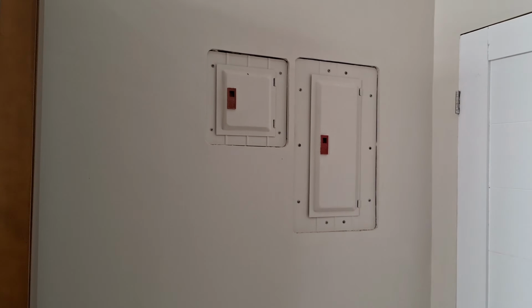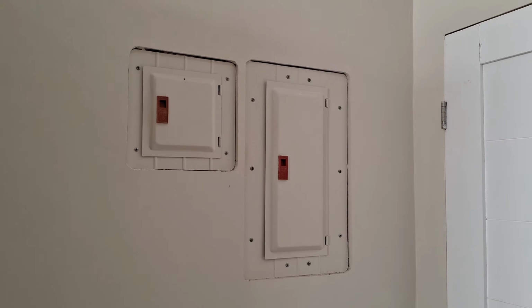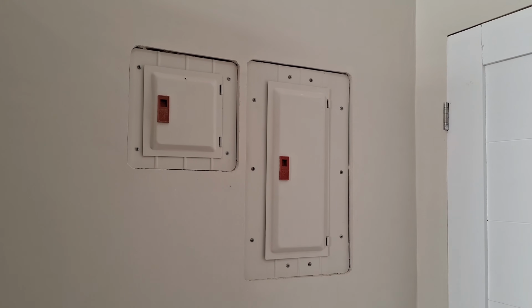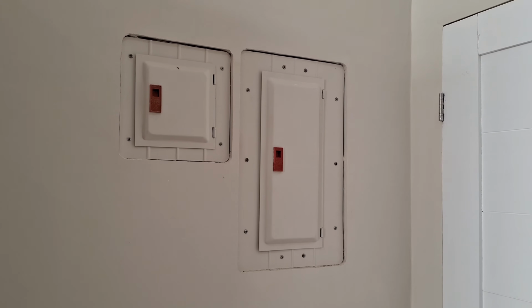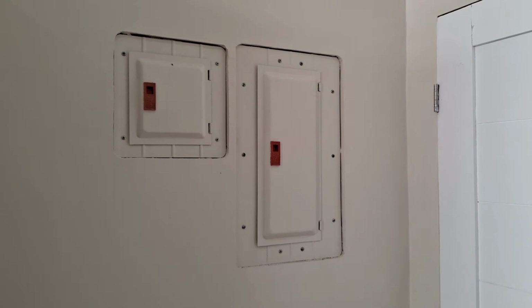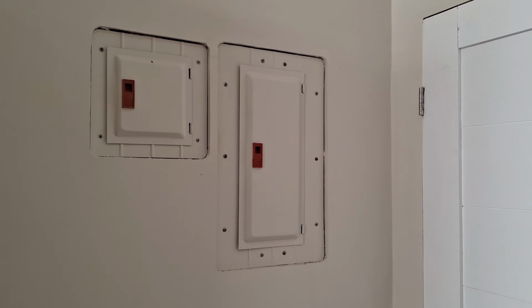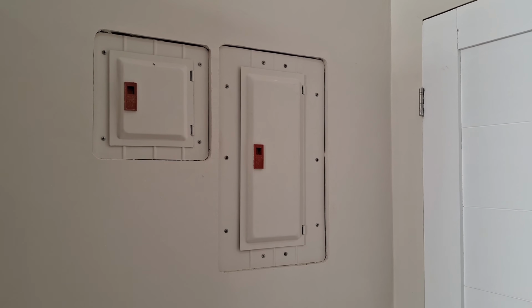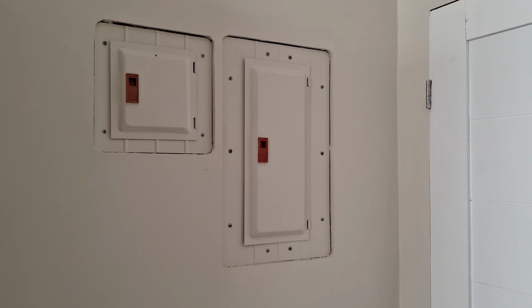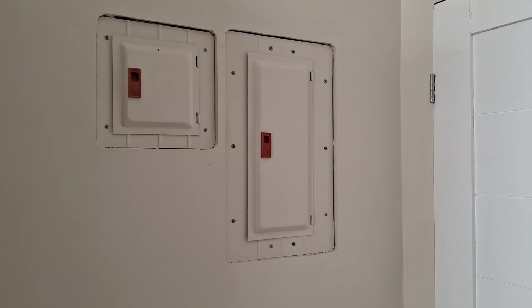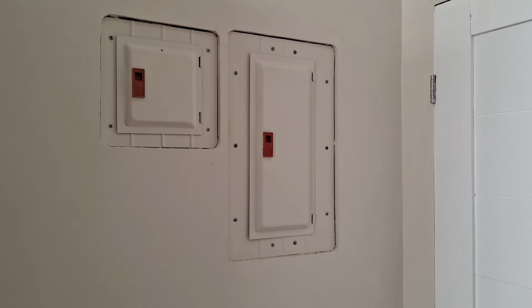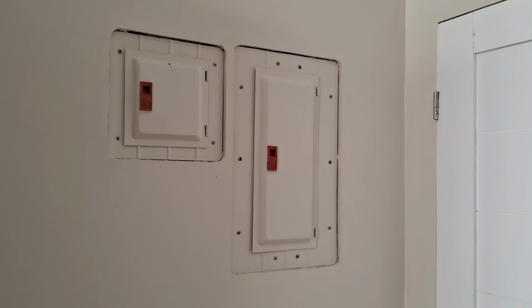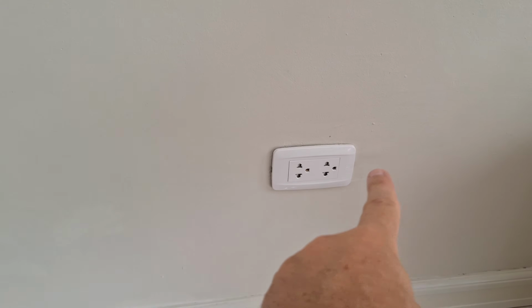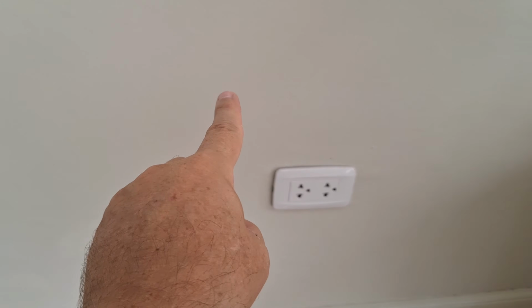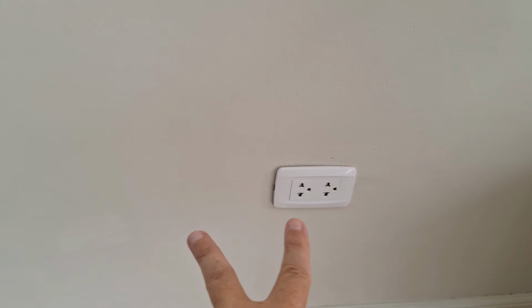The final option would be for someone buying and renovating a home, or building one, who brought a lot of 110 volt appliances with them. In our house, everything is wired 220, but you could wire your house both 220 and 110 at the same time - it would be an added expense, requiring an additional panel, additional circuit breakers, and running wire throughout the house. In our case everything is wired 220 and horizontal, but in that scenario each 110 outlet would be vertical next to the 220 one, and you'd have double the conduit.